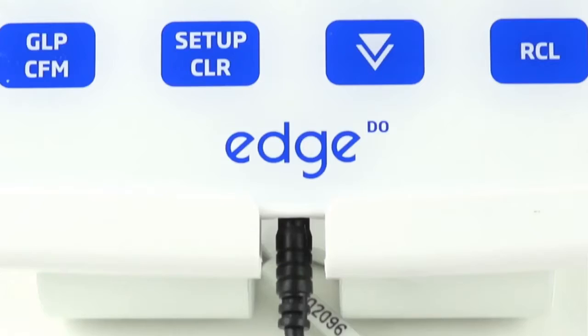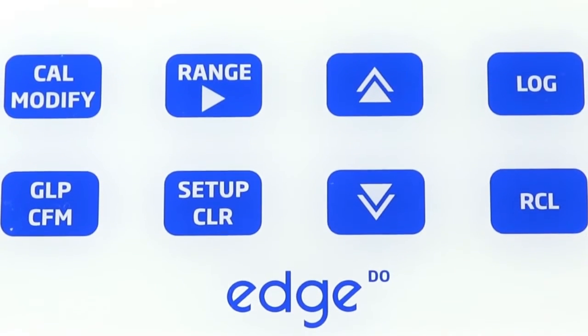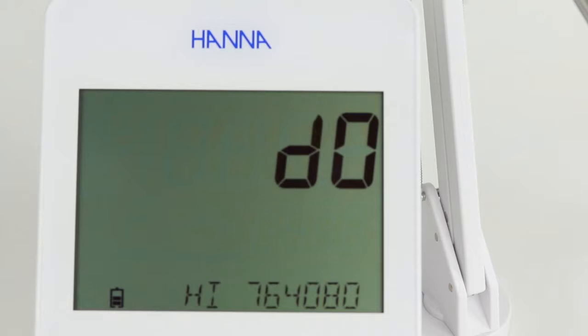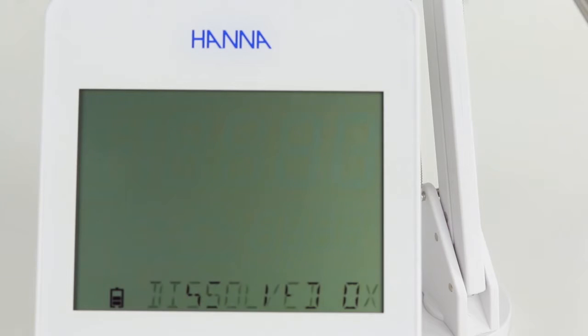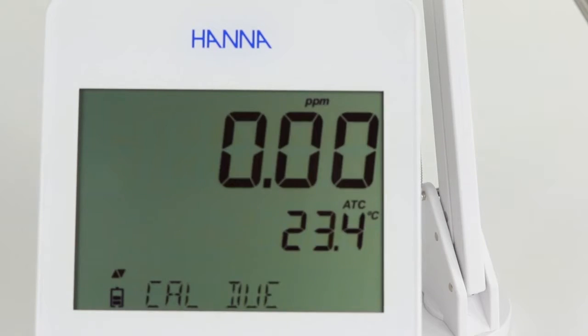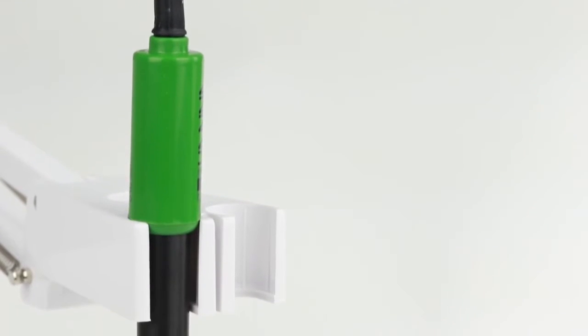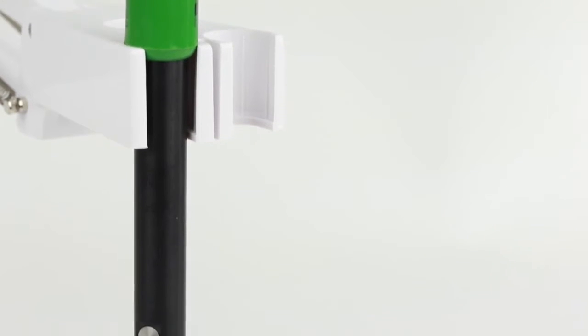Ensure that the probe is fully inserted into the 3.5mm connector. Once connected, the meter will automatically recognize the probe and enter dissolved oxygen measuring mode. Edge uses a polarographic dissolved oxygen sensor, so we recommend waiting 10 minutes for the sensor to stabilize. After 10 minutes, you can begin calibration and measurement.